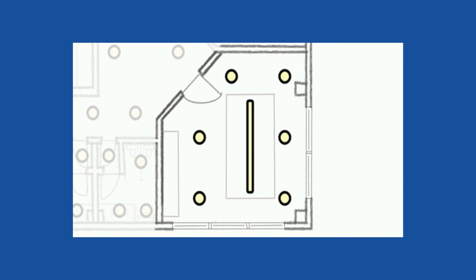We often see this in meeting rooms. This meeting room has a projector and a screen set against the top wall, and we want to create a DALI scene to set the lighting for when the projector is in use. For this projector scene, we want the lights closest to the projector screen to turn off so they don't throw additional light across the screen.